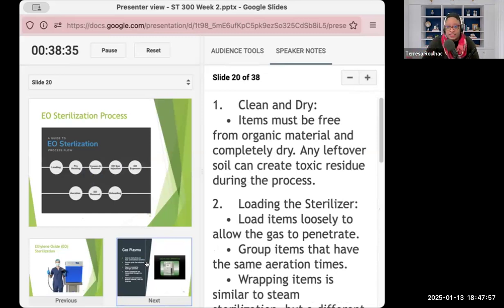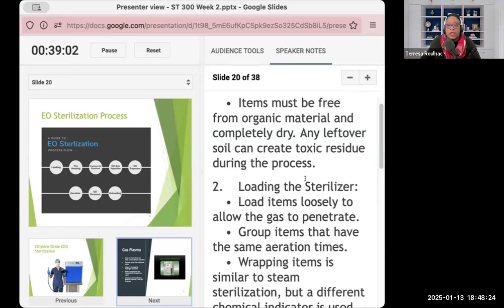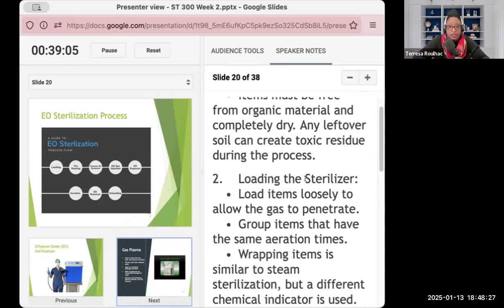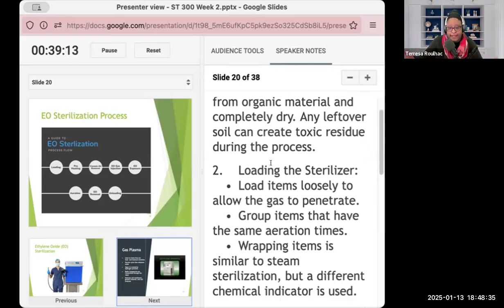With EO, ethylene oxide, items must be free from organic material and completely dry. Organic material, blood, tissue, that's all got to go. We can't have any bioburden. So you hear me say that term again, bioburden. These are going to be organic material left on an instrument after a case is over. Any leftover can create toxic residue during the process. So here you load items loosely because you want the gas to get to all of the parts. Group items that have the same aeration time, meaning items that have the same drying time. Okay.